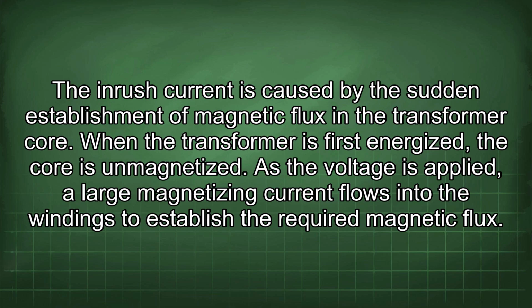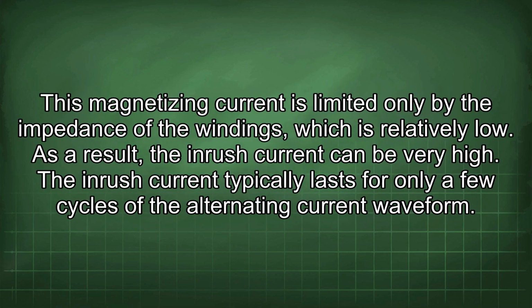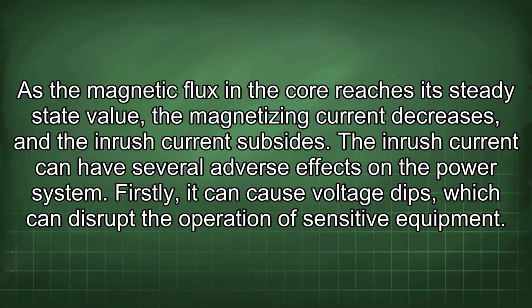The inrush current is caused by the sudden establishment of magnetic flux in the transformer core. When the transformer is first energized, the core is unmagnetized. As the voltage is applied, a large magnetizing current flows into the windings to establish the required magnetic flux. This magnetizing current is limited only by the impedance of the windings, which is relatively low. As a result, the inrush current can be very high. The inrush current typically lasts for only a few cycles of the alternating current waveform. As the magnetic flux in the core reaches its steady-state value, the magnetizing current decreases, and the inrush current subsides.